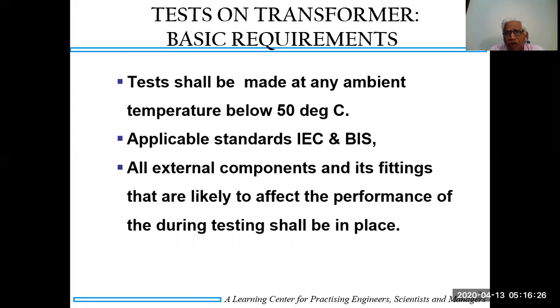That means there are so many components coming outside the transformer, they should all be fitted and then tested wherever required. In the case of a bigger transformer, let us say 10 MVA and above, they can't be fitted, so the manufacturer has to go there. After the transformer is fitted, he has to send his commissioning engineer to test all that and hand over the transformer.